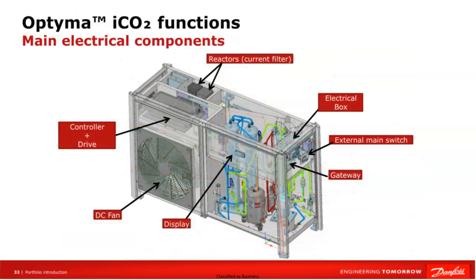This slide shows a drawing that highlights the main electrical components of the condensing unit and their location in the unit. The filters and the central controller, which is integrated with the inverter, are located above the fan. On the opposite side, we can see the electrical box, external main switch, and gateway. There is a display on the front of the unit that allows you to adjust and change settings just like in other Danfoss controllers. Now let's take a closer look at the other elements.